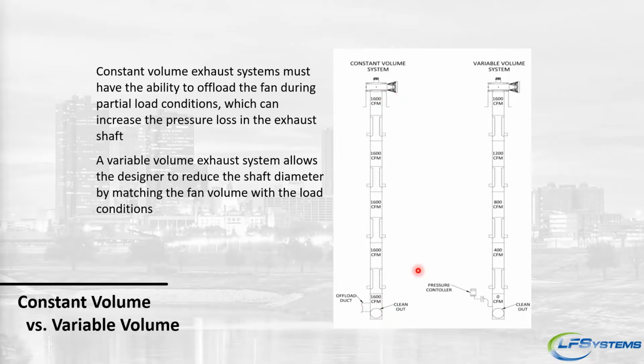It's a lot of air, especially in those slower times where you may not need the full 1600. So what we do is still size that fan for 1600 CFM, but instead of having it run continuously at a constant speed, we put in a pressure controller with a sensor. That controller is just going to maintain a very slight negative throughout this shaft. As dryers turn on, the pressure is going to build up and that fan is going to ramp up. As dryers turn off or as kitchen hoods are shut down, that fan is going to ramp back down.